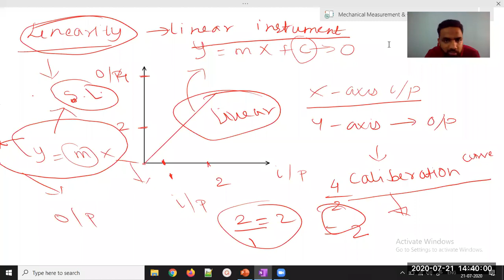Again, Anas is telling that when X is equal to Y, then such kind of instruments are called linear instruments. No, that is incorrect. X equal to Y doesn't mean that the instrument is linear. Even if X is not equal to Y, the instrument can be linear. For linearity, (Y2 minus Y1) upon (X2 minus X1) should be constant. If the slope is constant, the instrument is considered to be linear. I hope you're getting it. Is it okay? So what do you mean by linearity? Can you put it in the chat box?